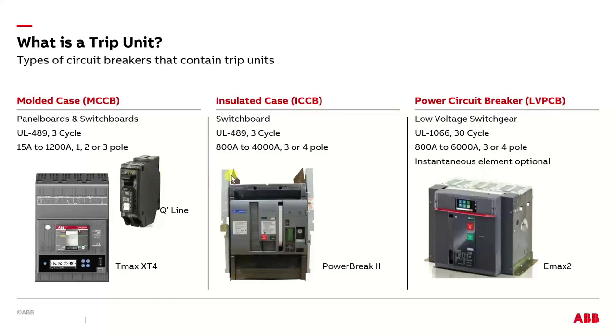So when you're back in molded and insulated case breakers, they all have this overlap on the instantaneous protection, so it makes it very difficult to coordinate them fully. And that's a loaded topic. But they do have an instantaneous overlap in most cases, where if you had a high enough fault current, you may trip the main versus the feeder breaker. You may trip, possibly and likely, both. So that's the difference that I'm trying to convey, the 489 versus the 1066.